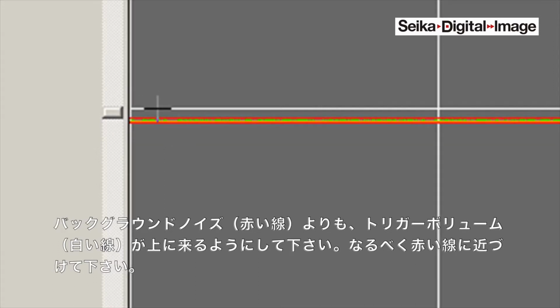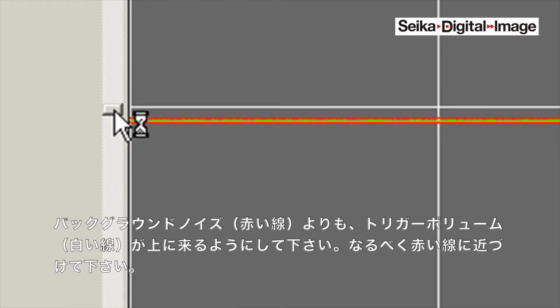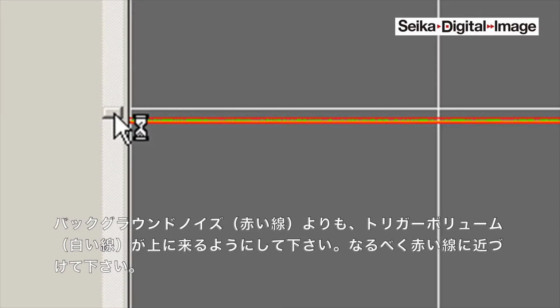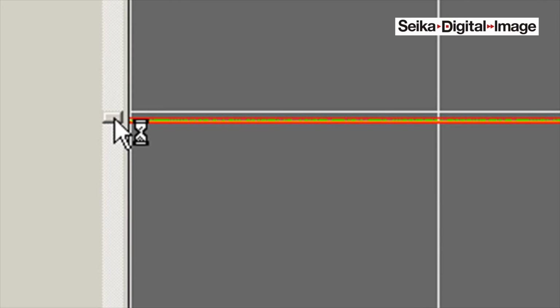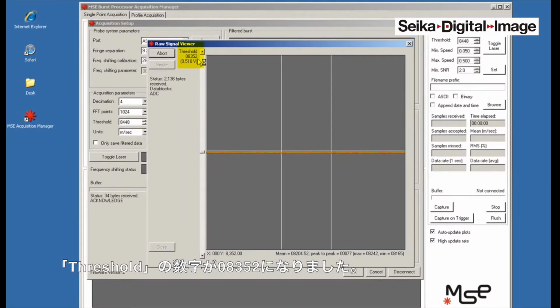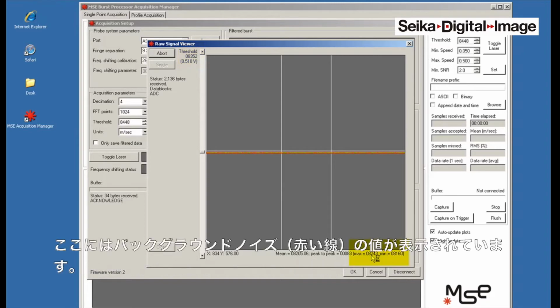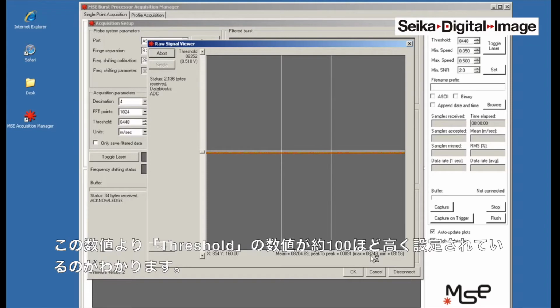We can tweak these to get higher data rates and so forth later, but as long as it's somewhat close to the top of the background noise, I can even bring it lower now. You can get as close as you want without going into the red zone. And what I'm doing is I'm just incrementing. So we have 8352 as a number, and here you can also, for each run, see the maximum and minimum value of the red lines. So it's about 8249 or 8250, and we are at 8352, so we're about 100 counts above that, and that's good enough to be above the background noise.